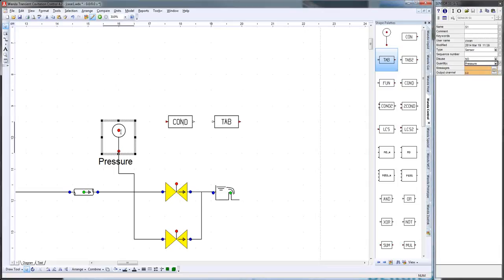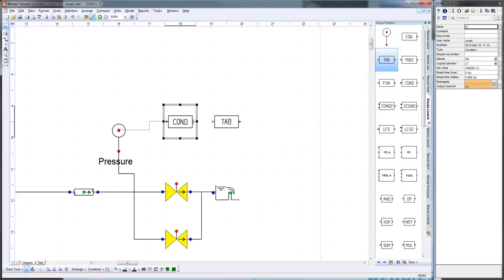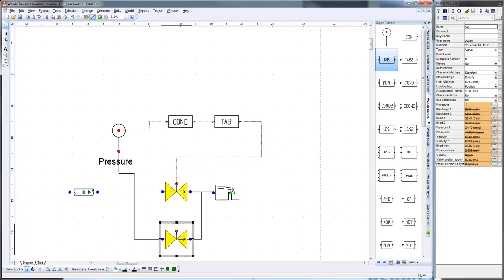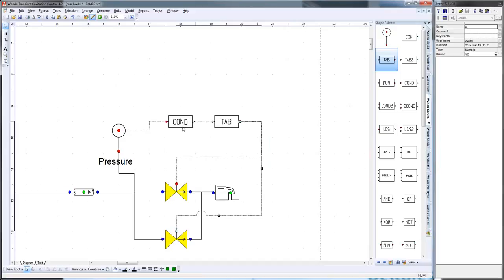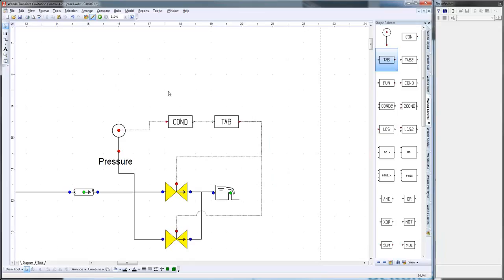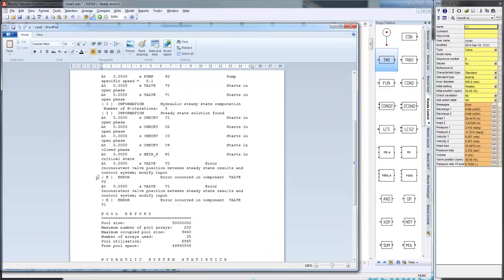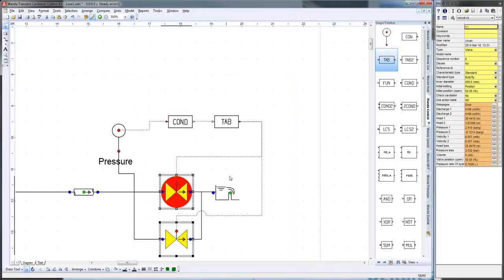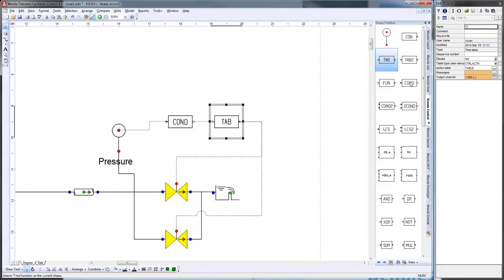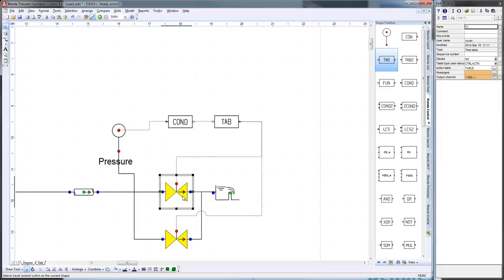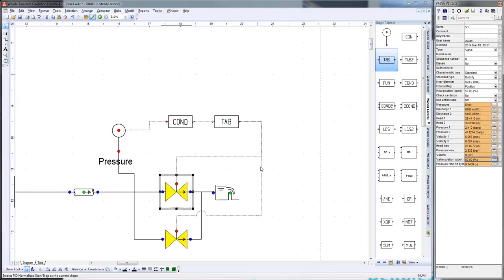So I now only have to connect everything. I'm going to connect the sensor to the condition - the measured value goes into the condition, the condition compares it and then gives either a zero or one, which I can put into the table. Then I connect the table to the valve. I have two valves, so I have to connect them both. Now I'm going to press Shift+F9 to start the steady calculation. I get the steady message files, and that means there is some error. You can see here: inconsistent valve position between steady state results and control system. The output channel is 1, so that means the valve position of 100%. Now looking at the valve position here, it's only 50% - there's the inconsistency.